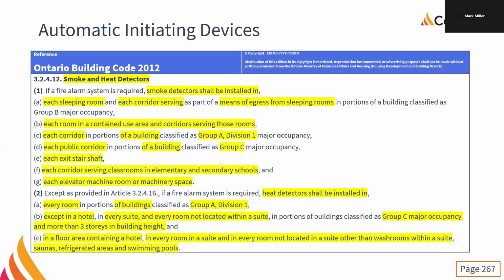We put one in each exit stair shaft at the top, of course. We put them in the corridors of elementary and secondary schools, and we put them in each elevator machine room or machinery space. Right? If we have an elevator machine room, it gets smoke detector. If we just have like an elevator machine cubby, because some of them are just tiny closets, yeah, it gets one in there as well. If we're dealing with escalators, the machinery space is typically right under the escalator. The smokes go in there. Right, so that is where we need to put smoke detectors specifically.